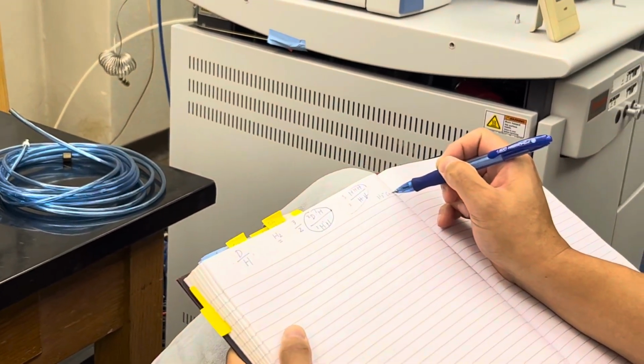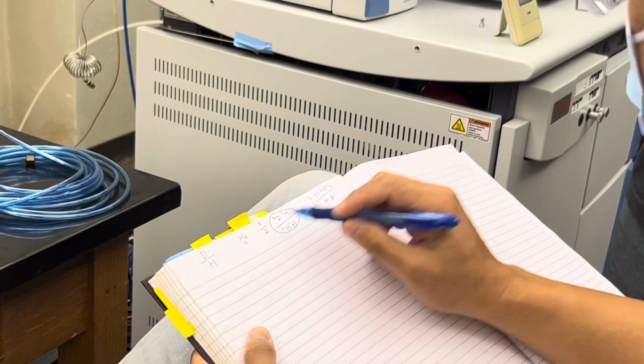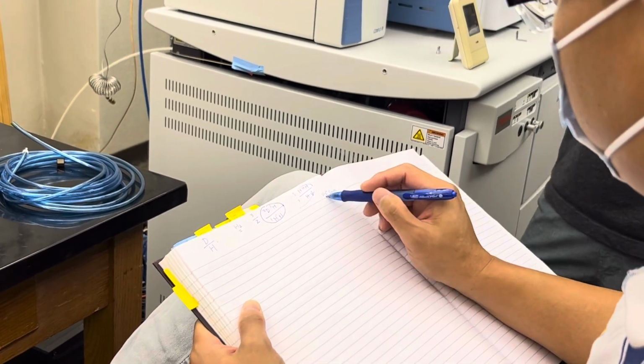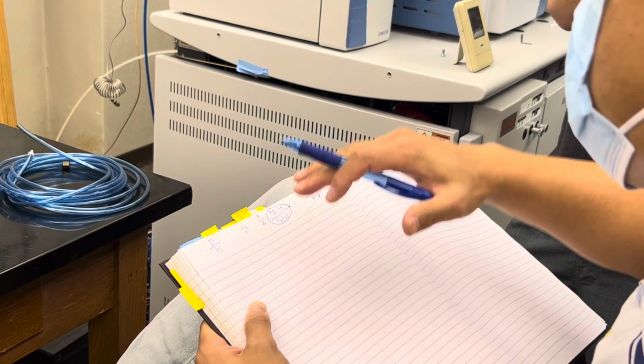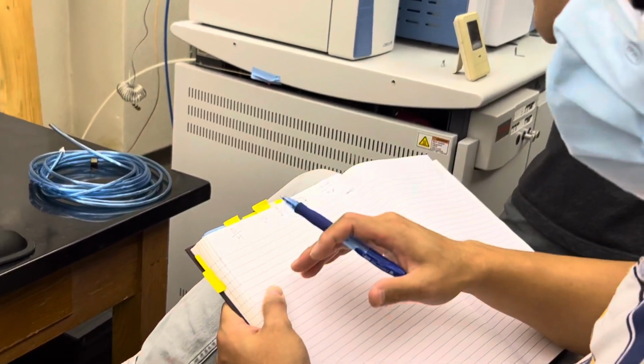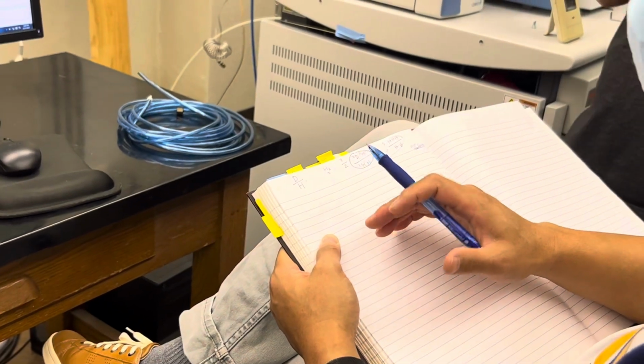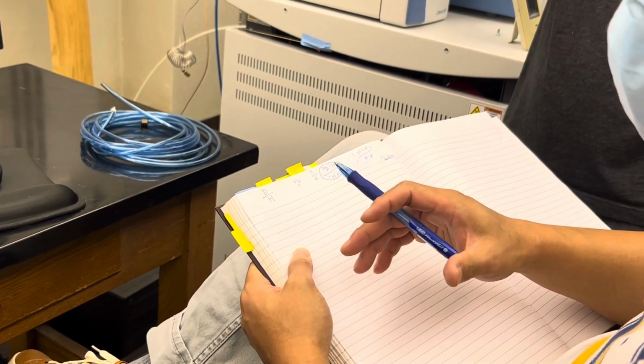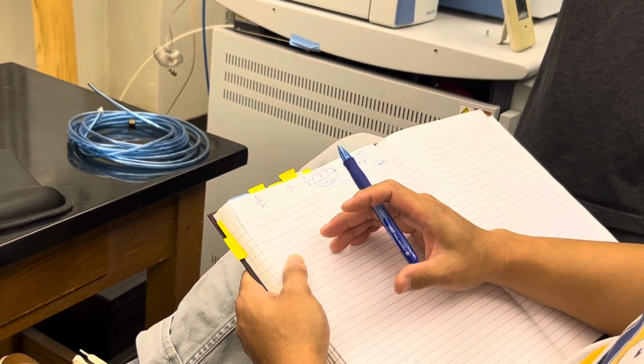Each day when you analyze hydrogen isotope, each day you have to check the H3 factor is below some value. It's supposed to be below 10. I think it's parts per million or something. I forgot the unit.